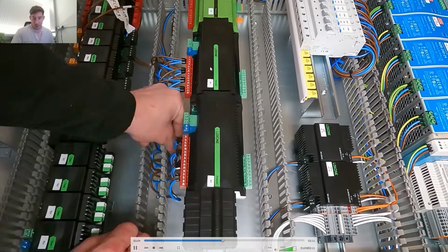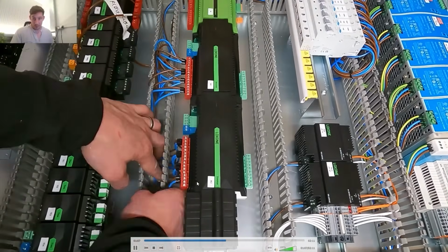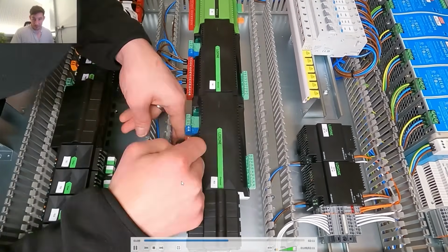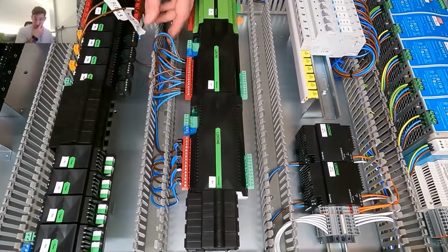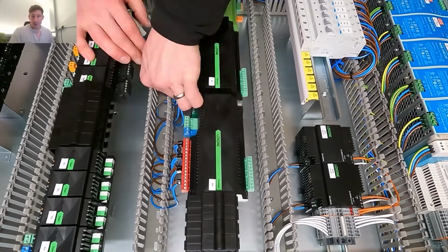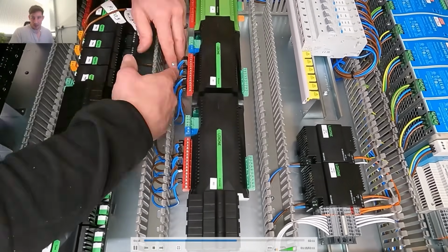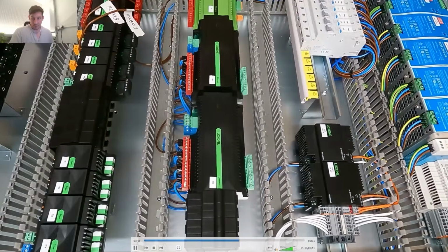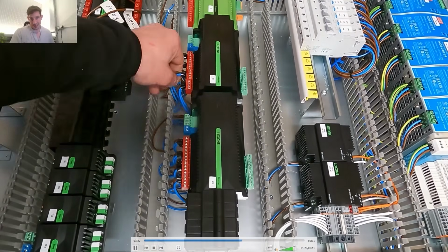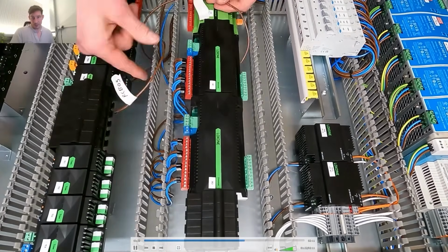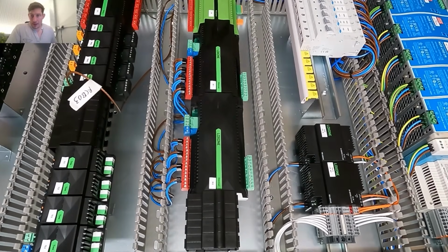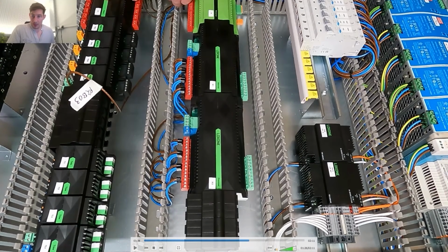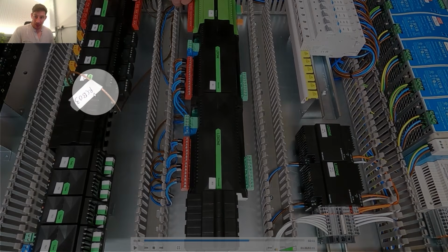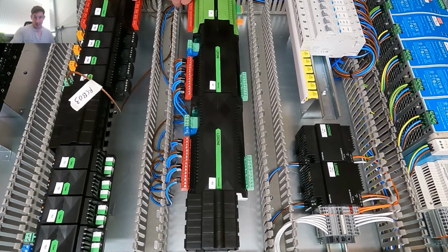Those double ferrules is where I'm looping in, looping out. Obviously the last one here, we're not looping on to anything else, but that's pretty much the dimmer extensions done. Just sorting that out, making it neater, so there's less cable filling up the trunking. You can see, when I added in the feed cables from the RCBOs, I labeled them just so I don't have to do a continuity test.